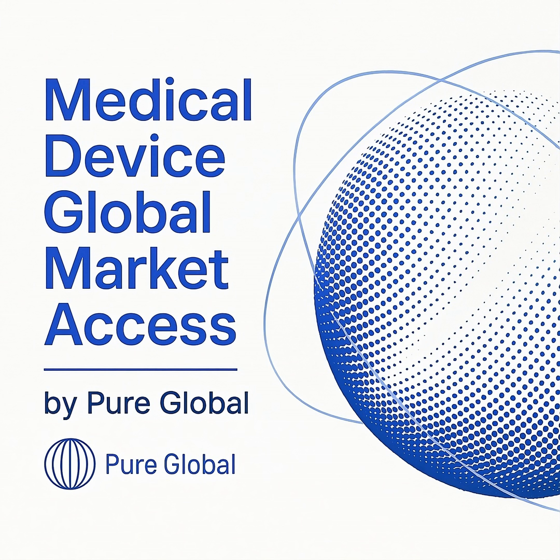The impact of this classification is profound. In the US, a Class 2 device generally means preparing a 510(k), while a Class 3 device means the much more resource-intensive PMA pathway. In the EU, any device above Class 1, and some within it, requires a conformity assessment from a notified body to receive its CE mark, which is the symbol of compliance.